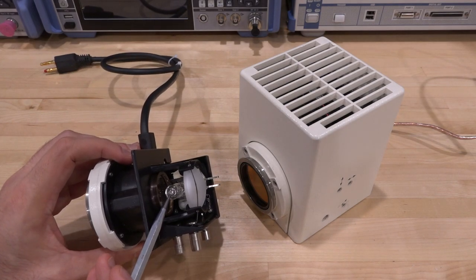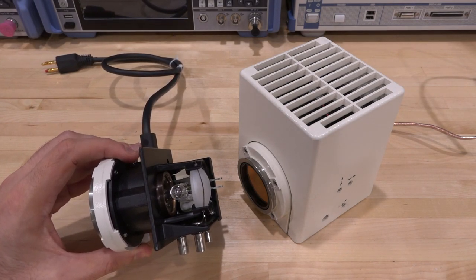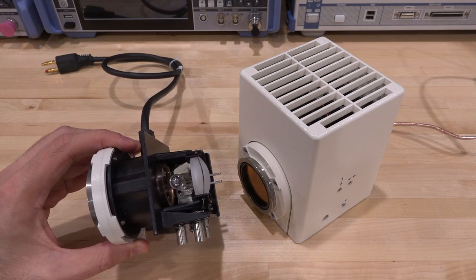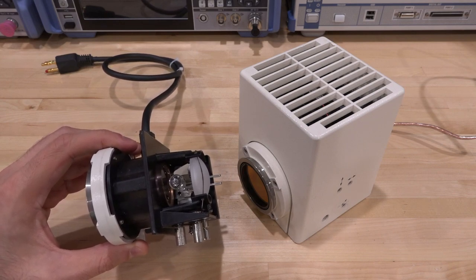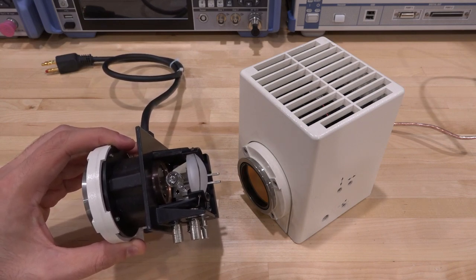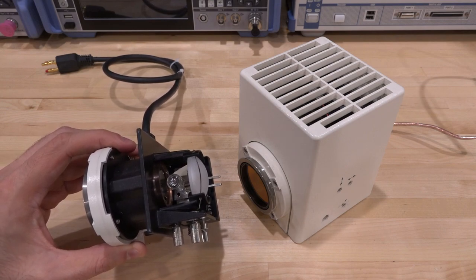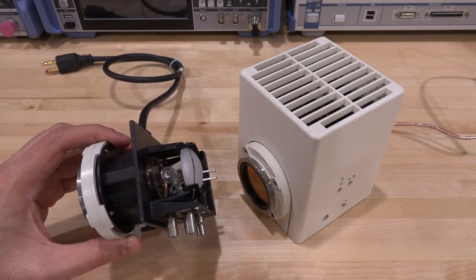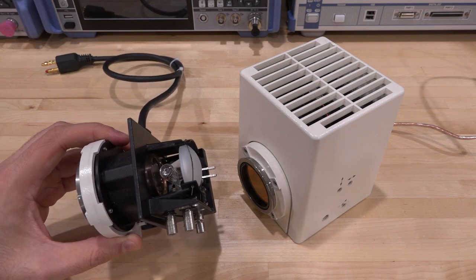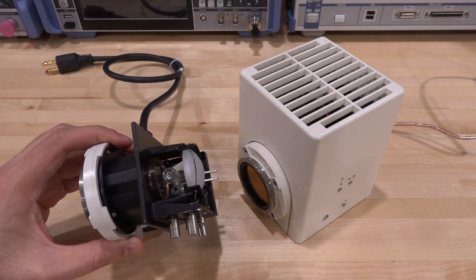That's one of the reasons they use the halogen lamp here. But halogen lamps have one major disadvantage: the color temperature coming out of them is a function of how much energy you put into them. And that's where the term degrees Kelvin actually comes from - it refers to what would be the spectral emission of a tungsten filament at that temperature.